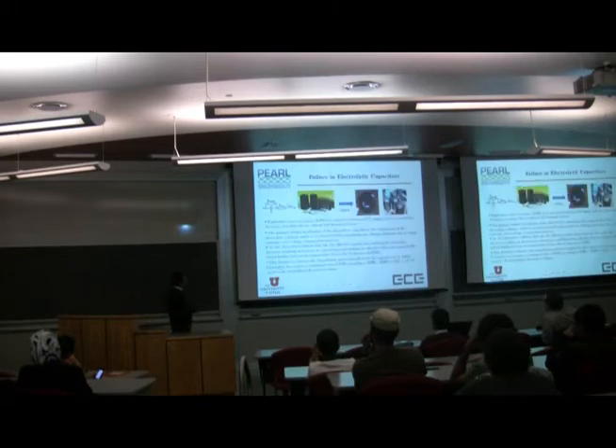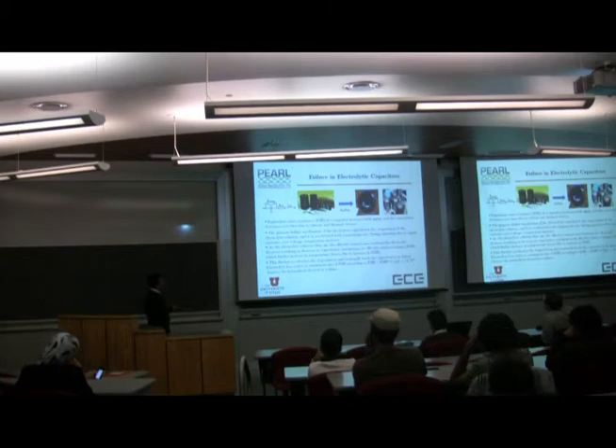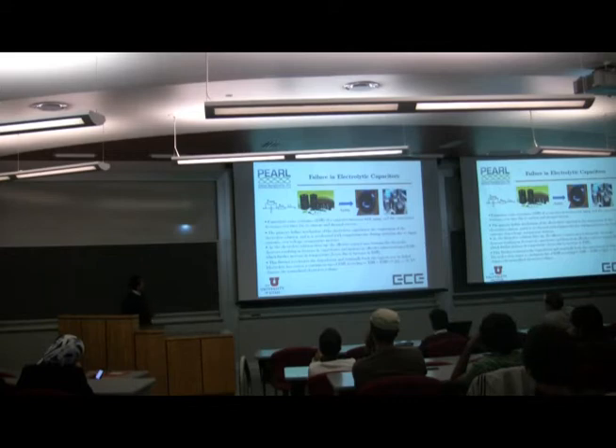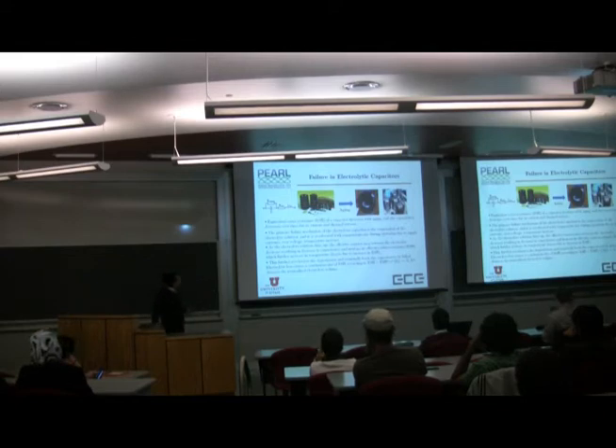We also have stress or degradation in capacitors. This is the equivalent circuit of a capacitor, and this is the ESR that I just mentioned, the equivalent series resistance. With time, the effective capacitance would go down, and the ESR would go higher than in the original capacitor. This is a healthy capacitor, or a group of capacitors. You can see a puncture or the presence of liquid coming out of the capacitor. So it has definitely been exposed to very high ambient temperature or very high voltage or current that causes this leak, and it bursts.